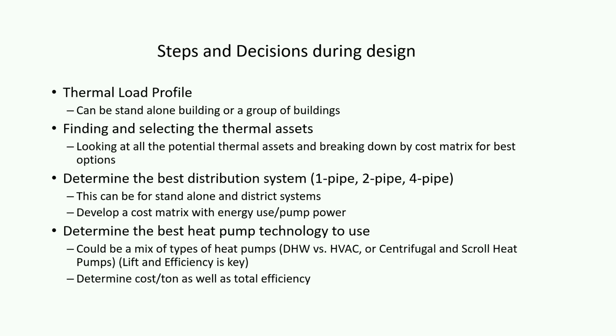Understanding the facade, how efficient the envelope is going to be, and of course the ventilation are all part of that. And then looking at your thermal assets, what are you going to have? Generally in a tall building you've got a lot of units, so you're going to have a lot of occupancy and a lot of wastewater. Is that an asset? Potentially. Geothermal underneath the building is obviously an asset. Are there piles? Can we use energy piles? That could be another asset. Maybe there's some air source opportunity to help hybridize the system if you can't do it all with one technology. So just understanding all the thermal assets on site that could potentially handle the entire load of the building and completely electrify it, because that's our goal, right? Be 100% electric, using very efficient technologies so we're not increasing demand on the grid. So going through that process early on is important.